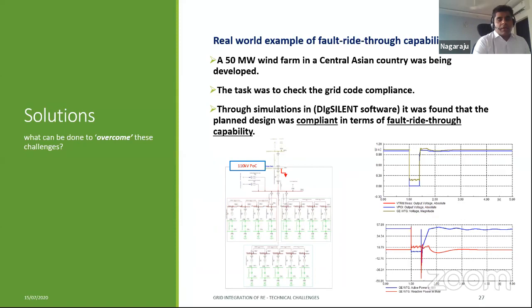Okay, then fault ride through in the same wind farm, the 50 megawatt one. The fault ride through requirement in this particular grid is very demanding. They need the wind farm to continue operating when the voltage at the connection point is 0 for nearly 650 milliseconds. I think 650 milliseconds is correct. That's a very demanding requirement for the grid.